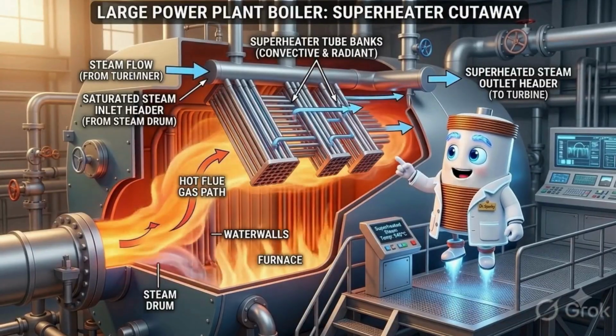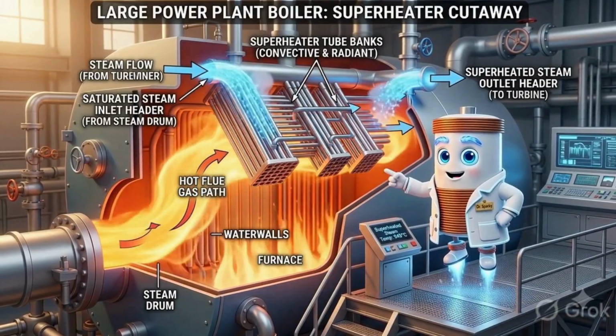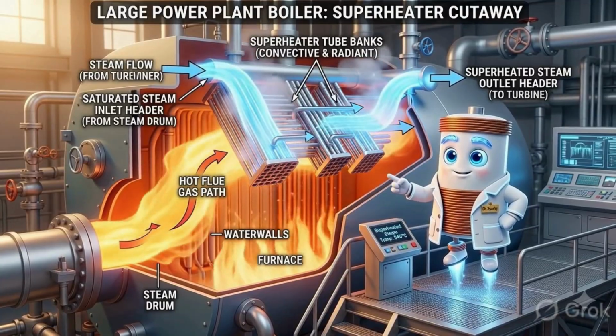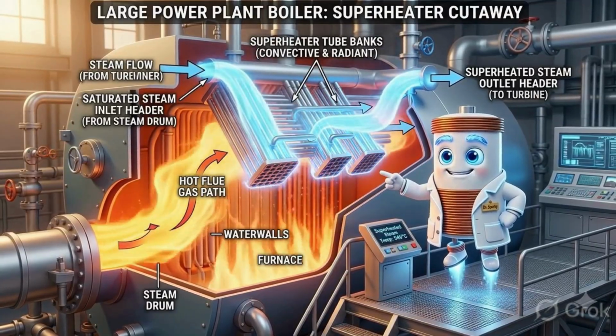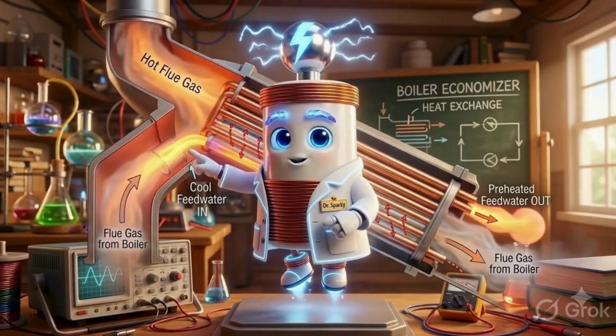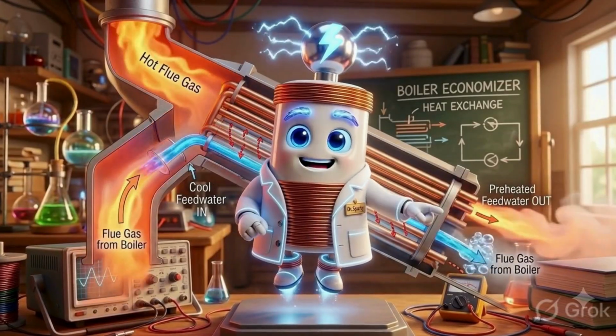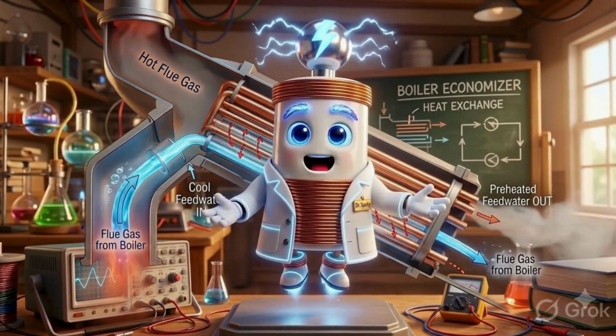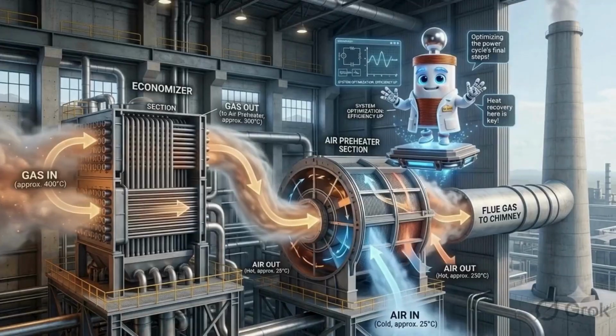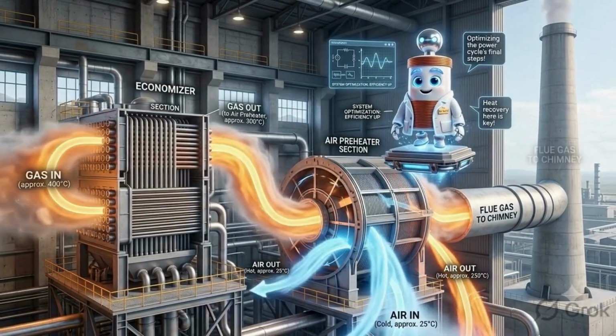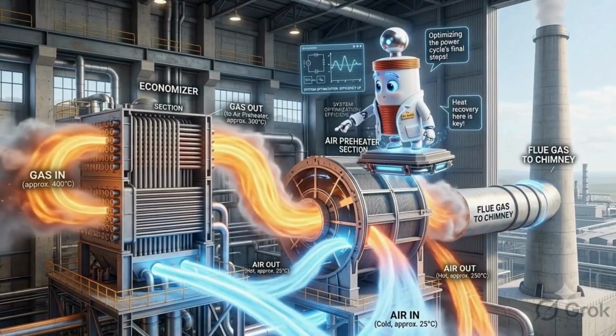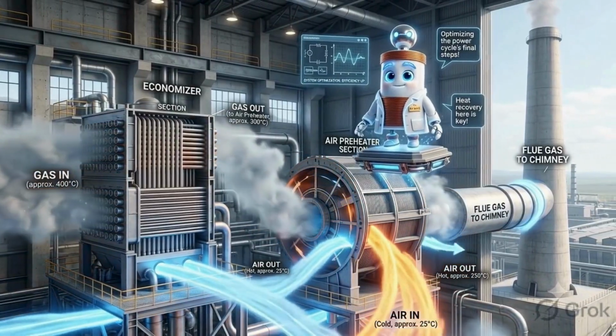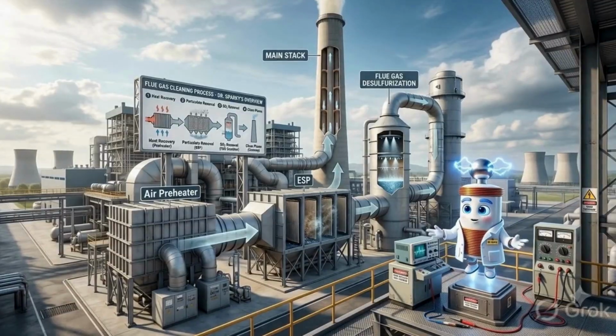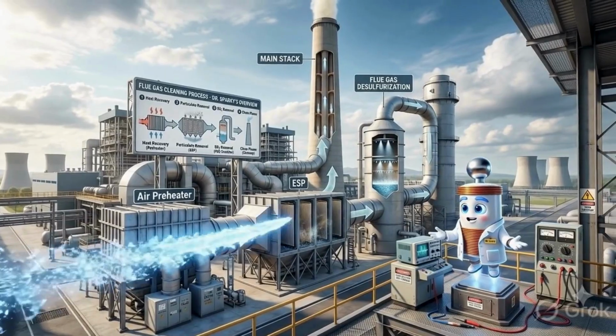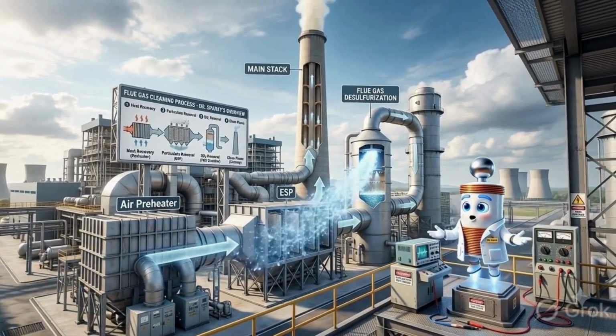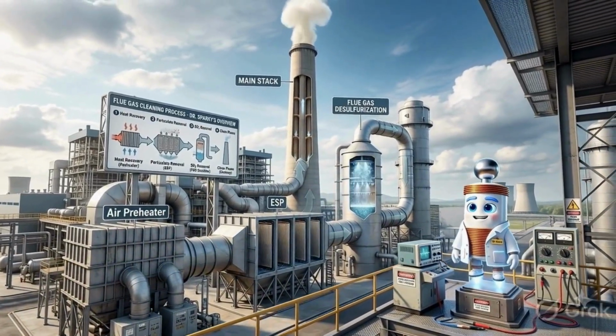First, hot flue gas transfers heat to the superheater. The superheater raises the temperature of steam before it enters the turbine. Next, the flue gas passes through the economizer. It preheats the incoming feed water before that water enters the boiler. After giving up more heat in the economizer, the flue gas reaches the air preheater, where it heats the incoming combustion air. Finally, the remaining flue gases travel toward the chimney. In a real plant, emission control equipment helps reduce pollutants before discharge.